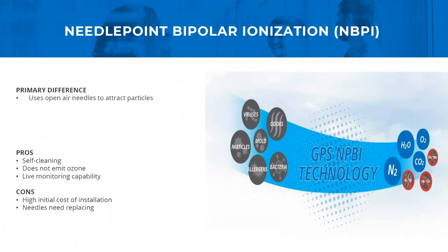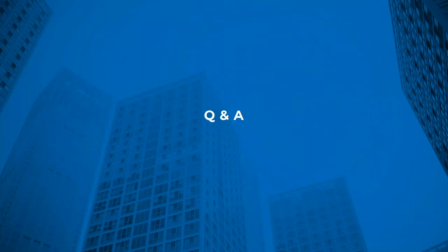And then the last question: of the four systems that you've talked about, which one do you feel the most confident in? First, I would definitely recommend changing the filters. Your filter is the best line of defense you have in terms of capturing particles that come through the airstream. So first off would definitely be upgrading the filters to a MERV 13. If you can reach a 15 without harming the quality of air going through the building or cutting down the CFM, I definitely recommend going to a higher MERV rating. The higher the MERV rating, the more particulates it catches, and the smaller the particles that get caught in the filters. From there, we've done a ton of research with needlepoint and feel very confident with it. Having that live active monitoring, measuring that you're actually producing enough ions through the airstream, is invaluable. So if I were to rate it, first would be your filter upgrade and then a needlepoint system.